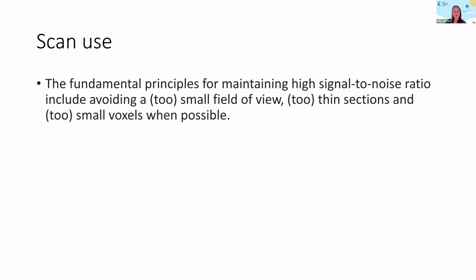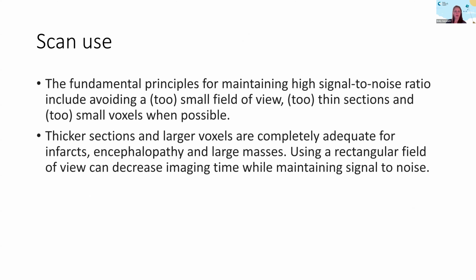So the fundamental principles for maintaining a high signal to noise ratio include avoiding too small a field of view, too thin of sections, and too small of voxels when possible. The signal is the image that we acquire, and the noise is the extra degradation that can happen from either movement or the equipment. And so you want to get good quality images that have a low amount of noise or degradation.